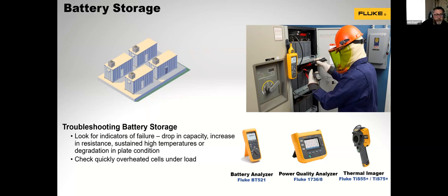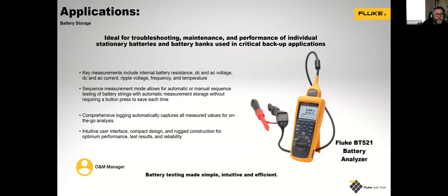With the battery analyzer, you're looking for drop in capacity, increase in resistance, that type of thing. So we'll just quickly double click on the BT521. It will measure internal battery resistance, DC and AC voltage, current, ripple voltage, frequency, and temperature. Because you've got many cells that you're measuring, you can set this to an automatic sequence. So you're taking many measurements that you can export for further analysis. You can log automatically if you so desire, and it's fairly intuitive to use.